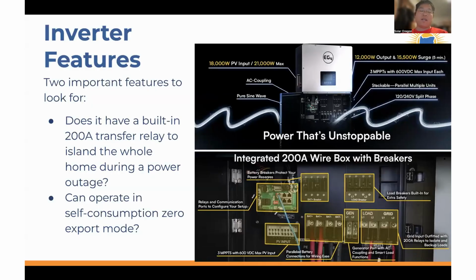So you can do things like: okay, I have 16 kilowatt hours of battery, and when I exhaust that or come close to exhausting it and the power is still out, I want the inverter to send a signal to the backup generator to turn on and continue to back up the house in island mode until this extended power outage comes back online. It can do those features as well.